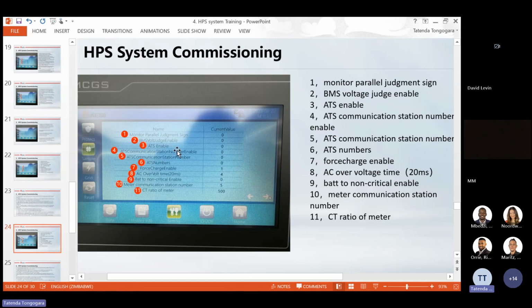And then we have ATS enable. If you are running with our ATS, you have to enable this, and then the number of ATS: if there are 2, you set it to 2. If it's 1, you set it to 1. And in the event that you are using our smart meter where you have critical and non-critical loads, you have to enable your smart meter, and then you put your CT ratio of the meter. You just check the CT ratios, and that's the value that you put here.